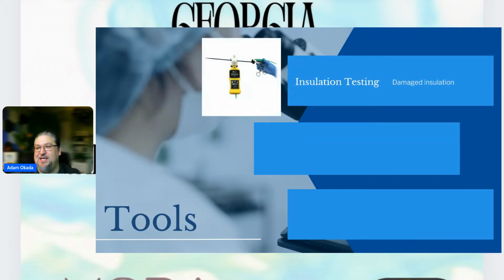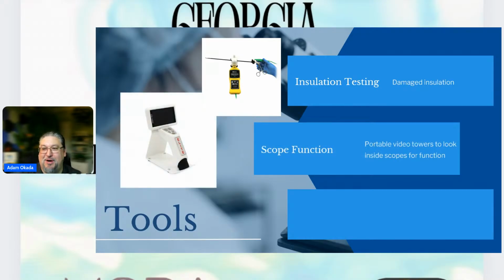So insulation testing, if you have damaged insulation, and we know this with insulated LEEP instruments, if you have LEEP vaginal speculums, or if you have insulated bipolar forceps, laparoscopics are the obvious one, but insulation testing should be done. We've seen so many infections occurring from insulation and the burns associated with insulation. It really is a big deal. And just like that story I told earlier on, insulation testing is something we really need to be doing every single time.